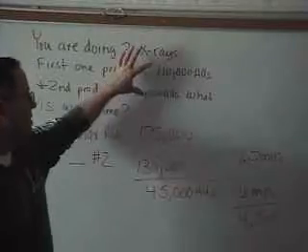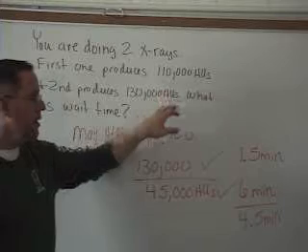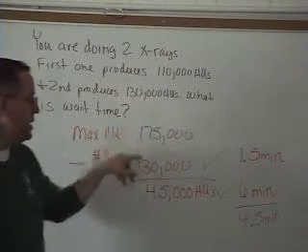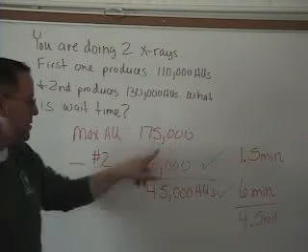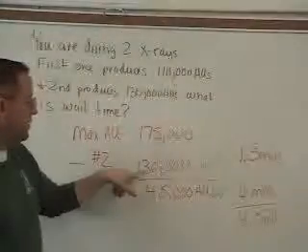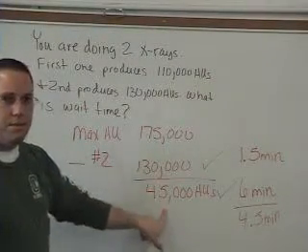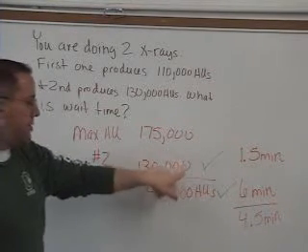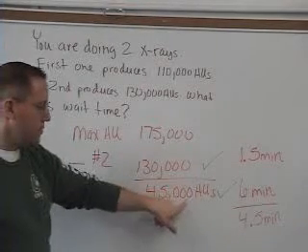If these two added together are more than the maximum, you can take the first x-ray but then you need to wait to take the second one. The way you figure that out is you take the maximum heat units — 175,000 — minus x-ray number two, which was 130,000. That gives you 45,000 heat units. Then you look up x-ray number two and also this result on the chart on page 81.